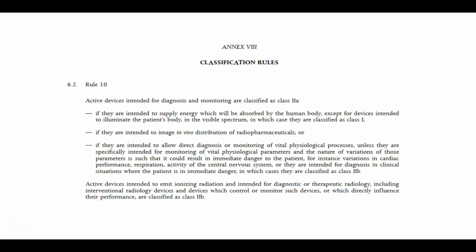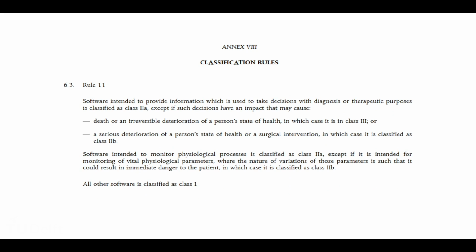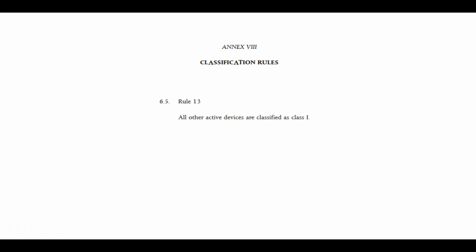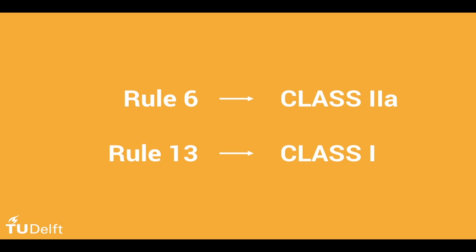Now, Rule 10 is about devices for diagnosis, monitoring, and radiology. Also not applicable. Rule 11 is about software, not applicable. And Rule 12 is about active devices that administer medicine, body liquids, or other substances, which our stapler also doesn't. So that leaves us with the last rule of Section 6, Rule 13. And this says that if none of the other rules in Section 6 apply, the active device is a Class 1. Check.